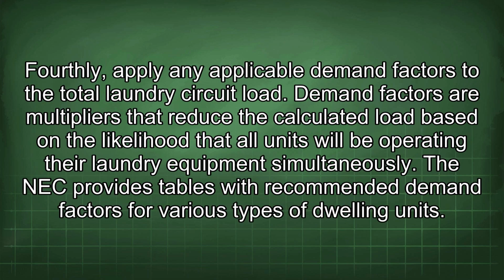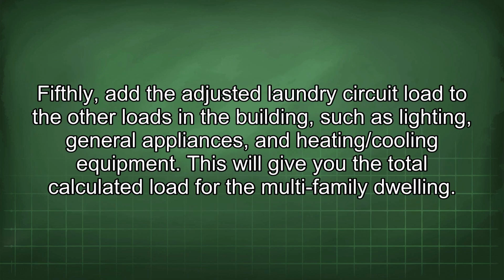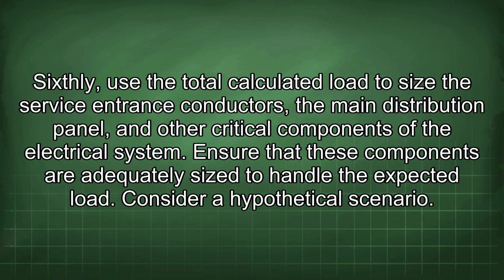Fourthly, apply any applicable demand factors to the total laundry circuit load. Demand factors are multipliers that reduce the calculated load based on the likelihood that all units will be operating their laundry equipment simultaneously. The NEC provides tables with recommended demand factors for various types of dwelling units. Fifthly, add the adjusted laundry circuit load to the other loads in the building, such as lighting, general appliances, and heating/cooling equipment. This will give you the total calculated load for the multi-family dwelling. Sixthly, use the total calculated load to size the service entrance conductors, the main distribution panel, and other critical components of the electrical system. Ensure that these components are adequately sized to handle the expected load.